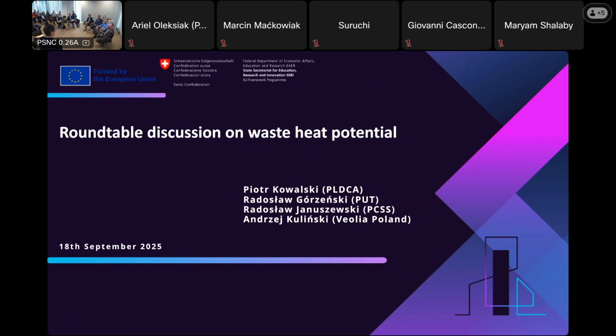If we look at district heating networks, they operate during the summer period at temperatures between 65, now in Poznań up to 70 centigrade, and up to 120 centigrade during winter. When we look at heat coming from data centers, depending on technology, it's between 25-30 degrees at minimum, and with DLC, direct liquid cooling, it rises to 40-50 centigrade, which means this heat has to be upgraded with high efficiency heat pumps to be supplied to the district heating network, with COP around 3, maybe 3.5 or even higher.